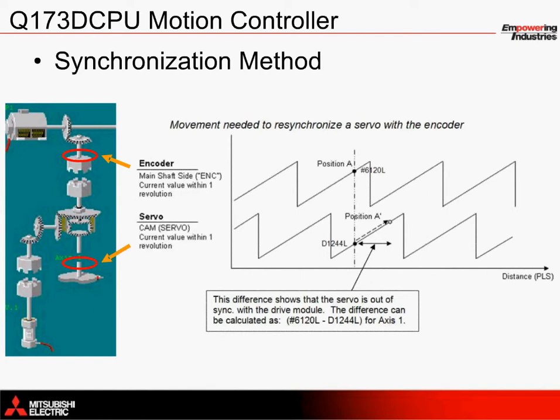In the phase drawing here, you'll see that the main shaft side value does not match the cam value since they are out of phase with each other. This can happen when a clutch opens suddenly and the drive or output module continues to move, or is commanded to move by the operator.